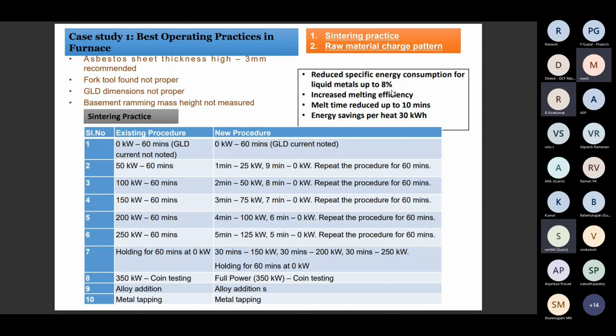These best operating practices reduce the specific energy consumption for liquid metal by up to 8%, increase the melting efficiency, and the melt time is also reduced by up to 10 minutes. Energy saving per heat is approximately 30 kilowatt hours. In the existing practice, they followed this step: 0 kilowatt for 60 minutes, and the GLD current is also noted. The new procedure is 0 kilowatt for 60 minutes, and GLD current is noted regularly. The second step is 50 kilowatt for 60 minutes continuously, in 1 hour. 50 kilowatt was maintained by the power capacity of the furnace.